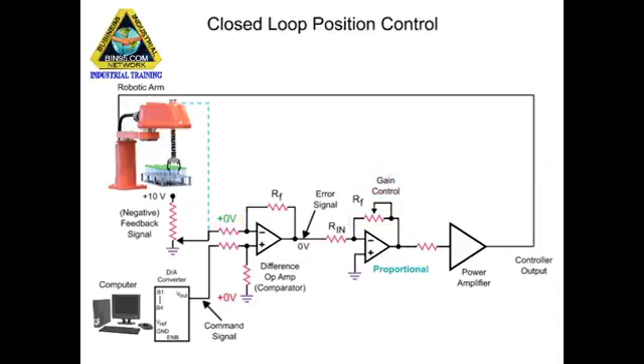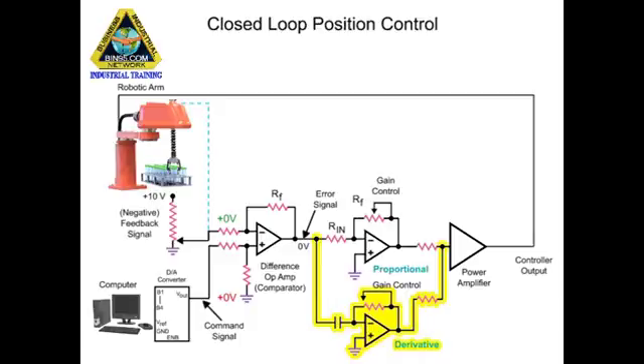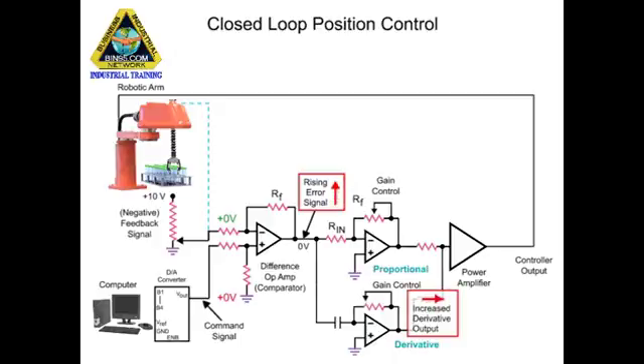To achieve a fast response time and minimize overshoot of the desired position, a derivative amplifier is added to the circuit. The derivative amplifier produces an output while the signal applied to the amplifier's input is changing. As the arm lags behind the command signal, the error signal generated causes the derivative amplifier to produce a voltage that adds to the output of the proportional amplifier.